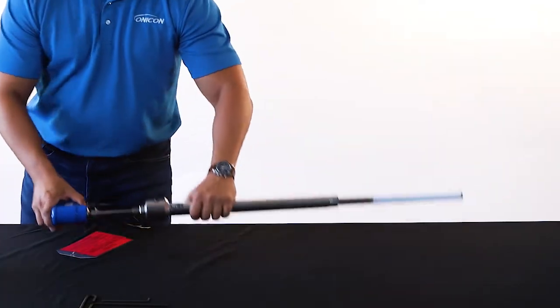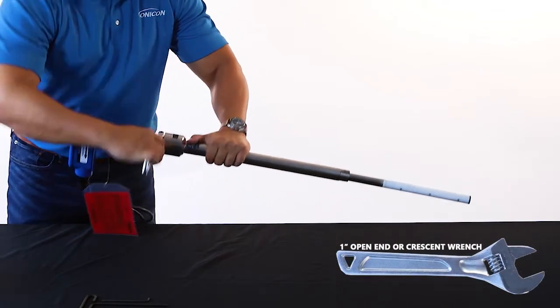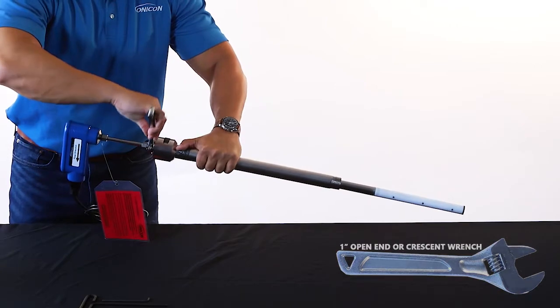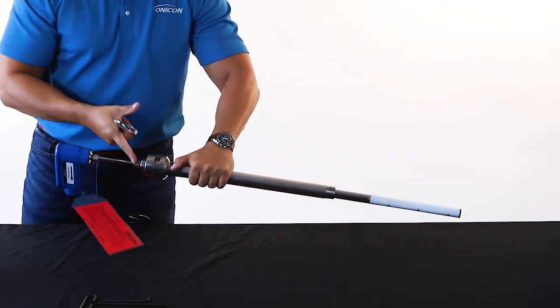With the flow sensor fully extended, use a 1 inch open end or crescent wrench to tighten the preload fitting completely. When done correctly, the preload fitting should be flush with the hot tap adapter preload housing.